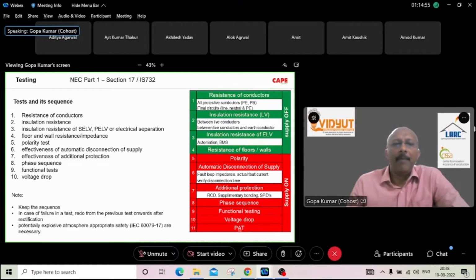I have also put the 11th test called PAT, Portable Appliance Test. The concept is, with these 10 tests, you get a very good electrical installation. But tomorrow, if you connect a faulty equipment, this may lead to a fire. That is a test which ensures that the equipment is healthy or not. Before connecting a portable device into your equipment, you have to be sure that your equipment is in a healthy condition. Now, in order to conduct the testing, you are supposed to keep the sequence. In case of any failure in the test, you are supposed to rectify the mistake and redo the test. You also have to have several safety measures to carry out these tests.